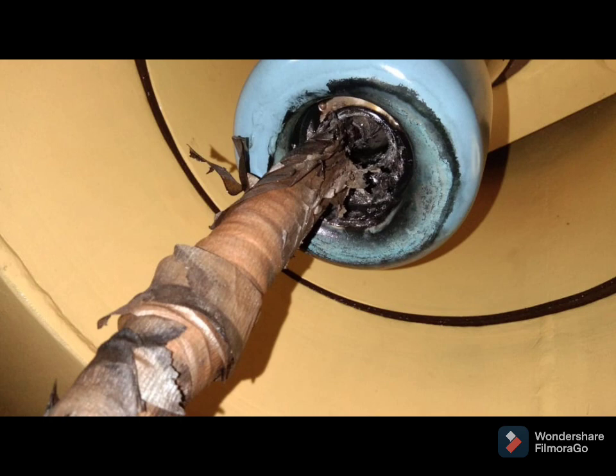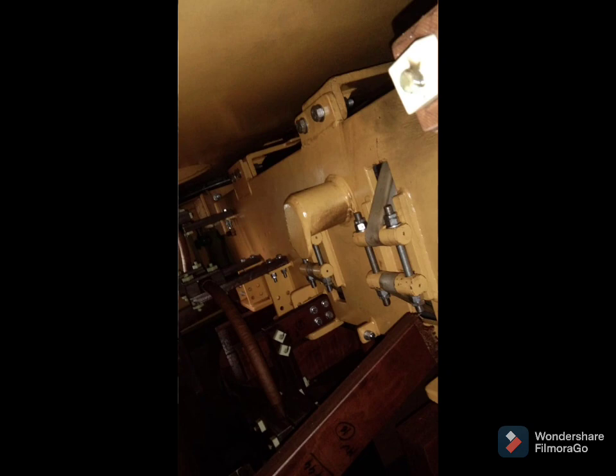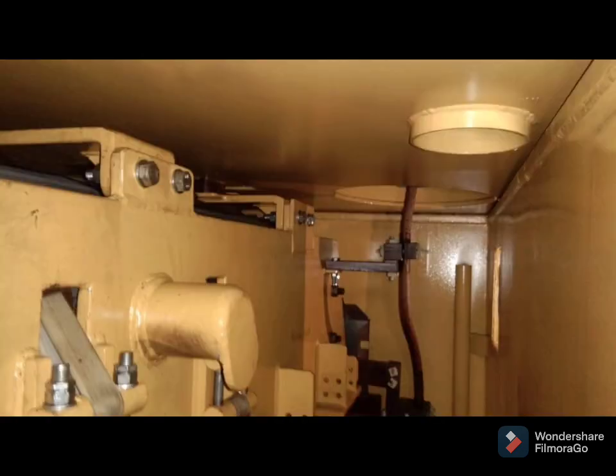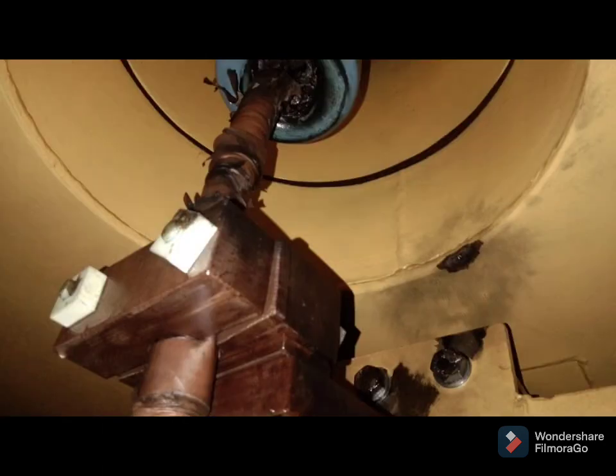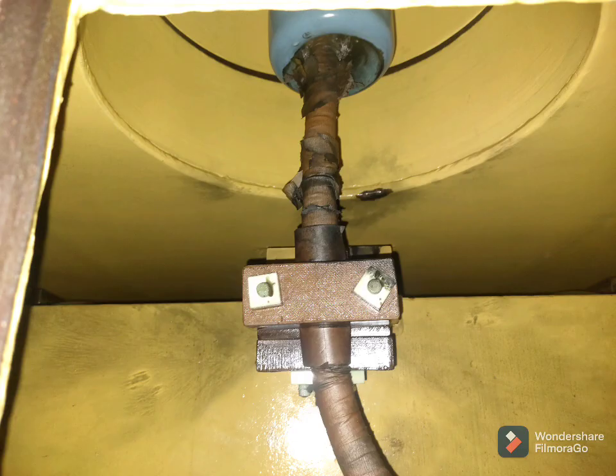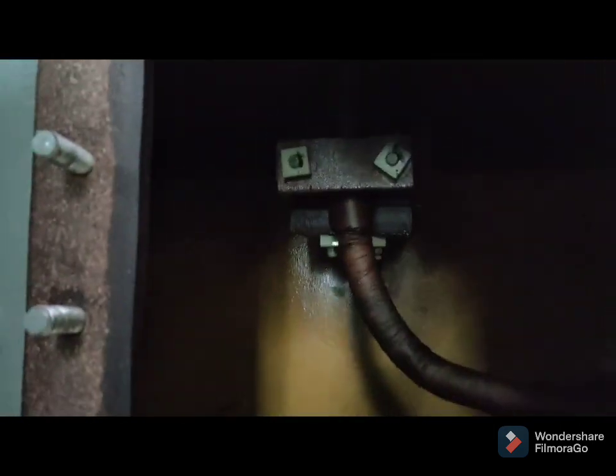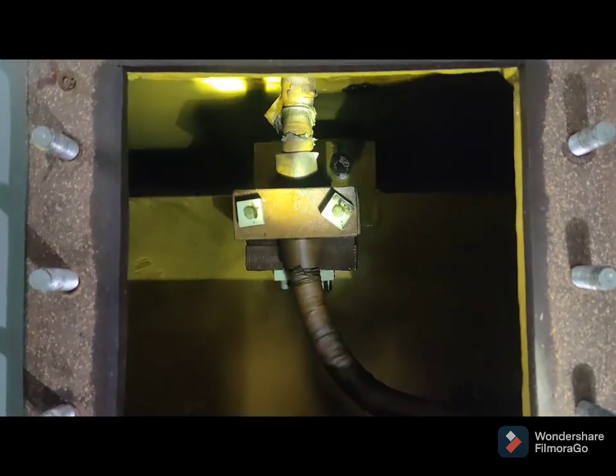You are seeing the affected transformers — the leads of the transformers and the bushings. Inside the pictures, the tour inside the transformer. You are seeing the cores, limbs, bolts, leads, etc. You are seeing the damaged lead inside the yellow phase bushing, and these are the damaged insulation failure matter inside the transformers.